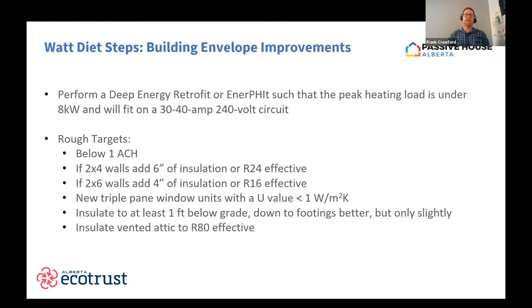And then finally, the last step, or one of the last steps of the Watt diet, is doing that deep energy retrofit or the building envelope upgrades. So either the Deep Energy Retrofit standard or the EnerPHit standard or various other standards. But basically what we're trying to do is get the building envelope improved enough so that the peak heating load, the highest amount of electricity or energy we need to keep that house warm on the coldest days, is about 8 kilowatts or less, which means it'll fit on one 30 to 40 amp 240 volt circuit.